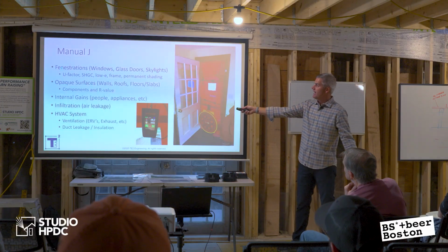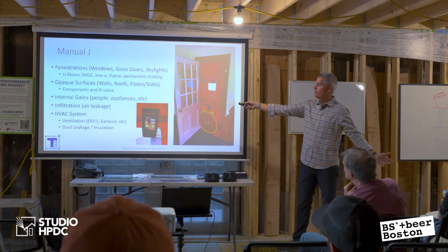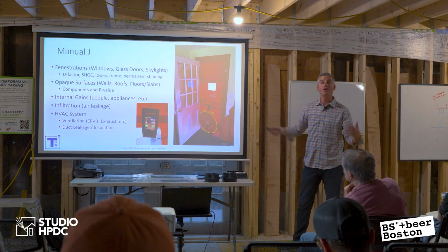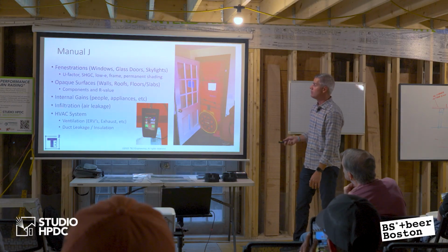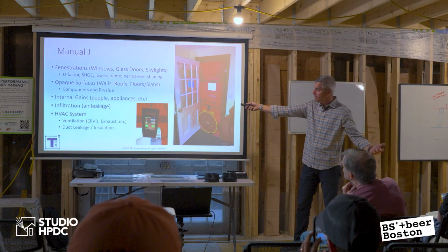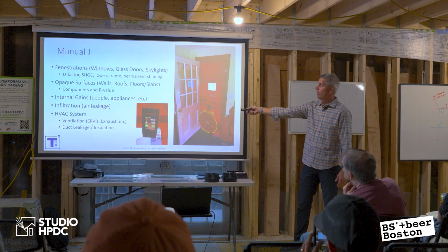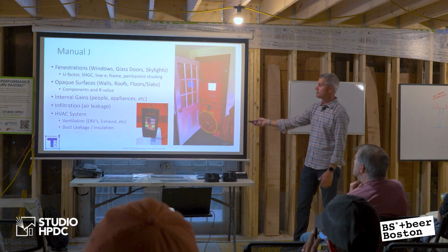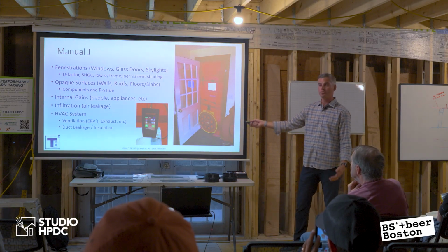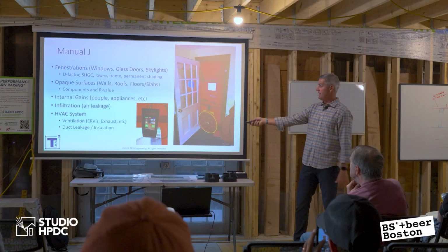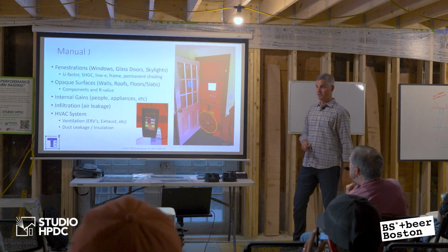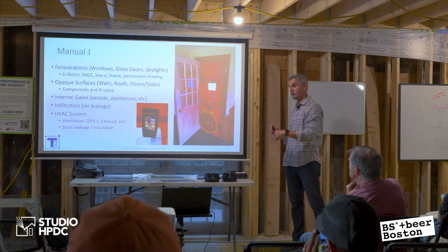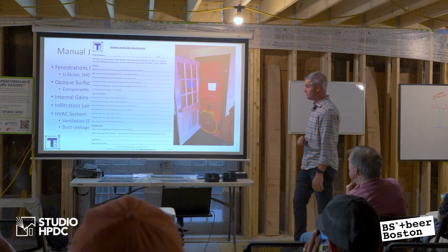So the Manual J looks at the U factor of all the windows, the skylights, the glass doors, the solar heat gain coefficient, how much solar heat comes through. Do I have any permanent shading, low E windows? I have to look at all the R values of all the opaque surfaces, internal gains, people, appliances, infiltration, how leaky the building is, HVAC system, the ventilation and the duct leakage, right? All that matters. It gets put in that software and we get a magic number, okay?